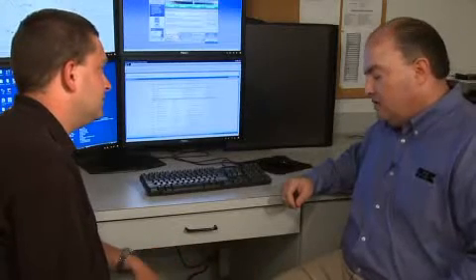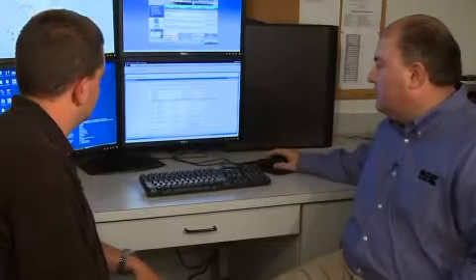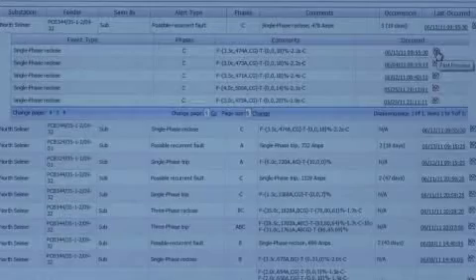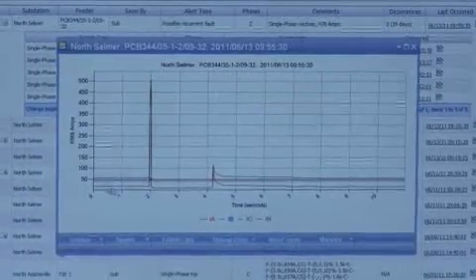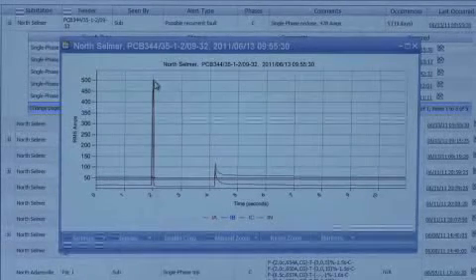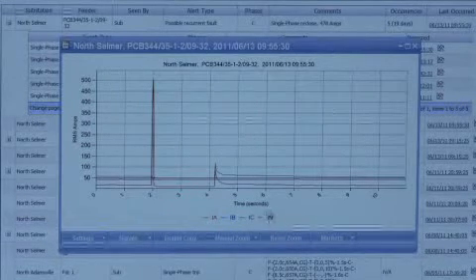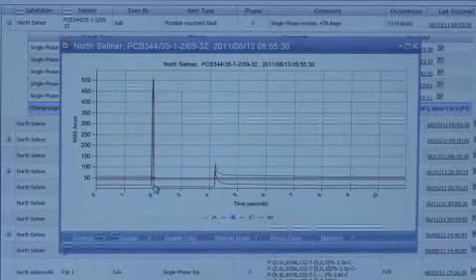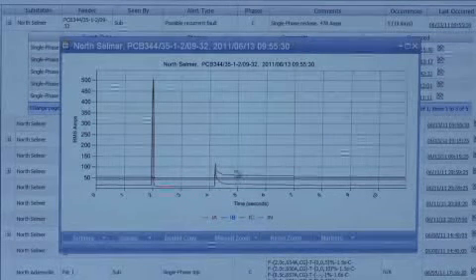And your members are having decreased outage time as well? Decreased outage time, decreased blinks — a blink like this. Not only the people on this particular feeder see it, but everyone served from that substation transformer on C-Phase is going to see that blink. The DFA also gives us the waveforms. Here are the RMS currents. We can see the fault — almost 500 amps of current there — C-Phase in the green and the neutral in the brown. So this is a C-Phase to ground fault. We see the breaker trip and the fault go away, and then we see the reclose, inrush, and the load is successfully restored.